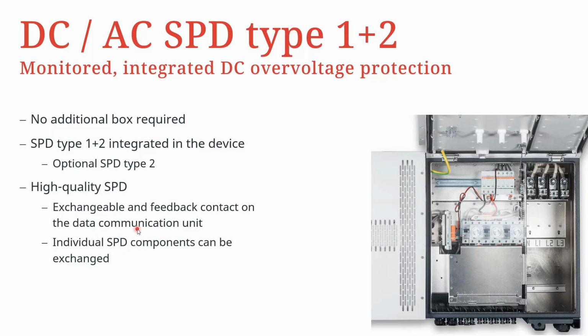And just to let you know that the SPDs come in different types. We have the type 1+2, and then we have the type 2. Both of them assure lightning and overvoltage protection, depending on your region. So for cases where you have a higher frequency of lightning, it's recommended that you go for type 1+2. In a region where you have lower lightning frequency, you can still go with type 2, because it also comes with lower lightning protection capacity.